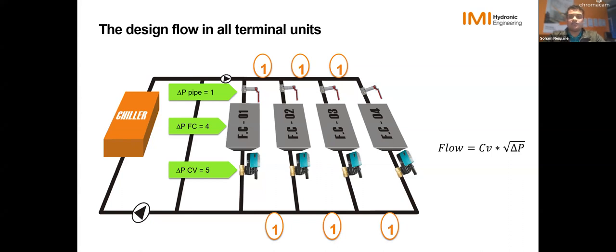So let's look at our first circuit with fan coil 1. The total pressure drop that you have on here is 10, right? So we've got 1 feet on the pipe, 4 feet on the fan coil, that's 5 total, and then 5 on your control valve. So we've got 10 feet of pressure drop. You go to the second circuit, we have the same 10 feet on this circuit as well, plus we have an additional 2 feet that we have to go through in our piping onto the second circuit. So we go to the third one, you add 2 feet more of pressure drop here, and that basically gives you 14. And you go to the last one, we've got 2 feet more, that gives you 16 feet of pressure drop. So now we just have a system that basically has variable pressure drop, as you can see, and there's no balancing added to it.